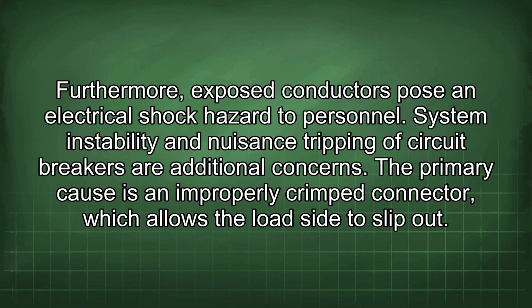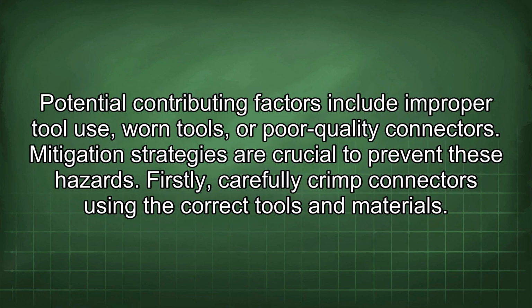System instability and nuisance tripping of circuit breakers are additional concerns. The primary cause is an improperly crimped connector, which allows the load side to slip out. Potential contributing factors include improper tool use, worn tools, or poor quality connectors. Mitigation strategies are crucial to prevent these hazards.